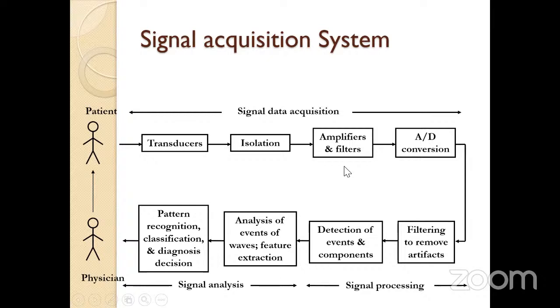Then we have amplifiers and filters. Whatever signal we are measuring from human beings is of very low amplitude. Amplitude is measured in terms of voltage. Very low amplitude means in the order of microvolts, millivolts, and volts, but biosignals will be mainly in the order of microvolts and millivolts. In order to drive any higher end system, we require at least 5 volts. So from millivolts and microvolts, we need to raise it to a voltage level so that it can be used to drive the further circuit. So this is the function of amplifiers, which amplify the signal.